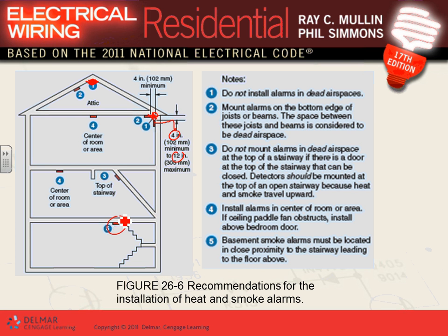Any comments, any questions about where you need the smoke detectors and how you install them? Can I have thumbs up, Chad? We understand that one. So we need them in every bedroom, hallways adjacent to bedrooms, every level. Where do you install them? You can't install them in corners like these, 4 inches to the ceiling. If you're on the wall, you have to stay within 4 to 12 inches from the bottom, right in this area.